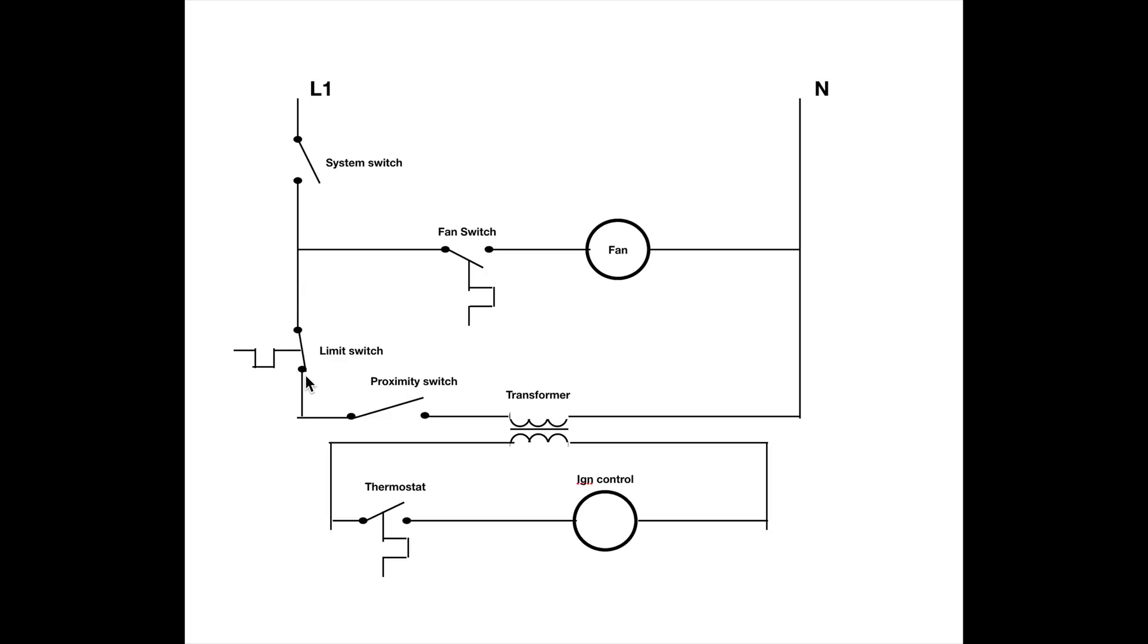I got a limit switch here. Now, the limit switch all it really does is shut off the transformer here which shuts off the entire low voltage for the ignition control. So the power goes through the limit switch, if the proximity switch is closed, meaning someone's out there, that's going to energize the transformer and the transformer is going to be able to send power through the thermostat and if it's closed, if it's cold enough out there, then it sends power to the ignition control.